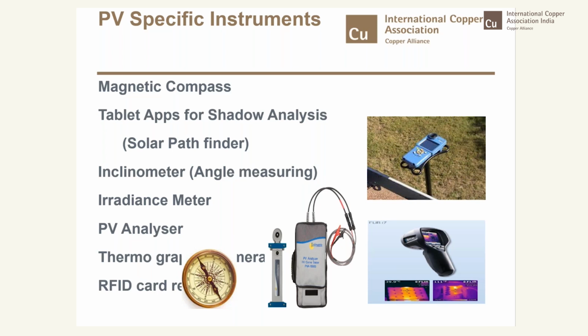And the PV analyzer is an equipment which will give you the PV curve, how it is traced at site. An analyzer is a very key instrument during the pre-commissioning test. And then we need thermographic cameras, which can identify any hotspots, which may be due to some internal damages of the cells, or excessive shadow can cause hotspots to be created. So these things can be captured in a thermal camera, a thermographic camera.